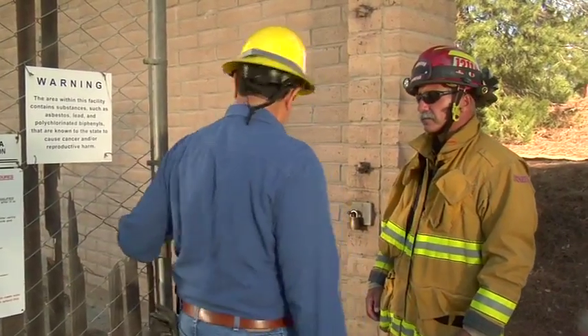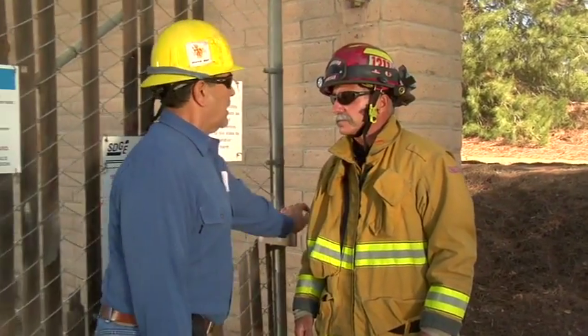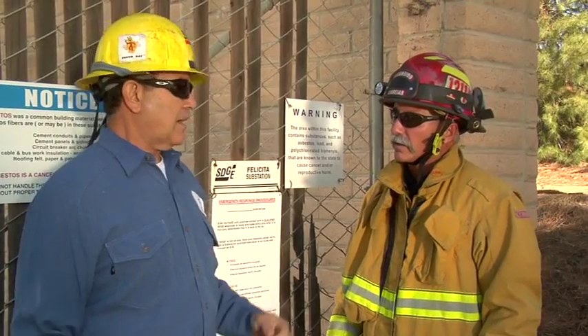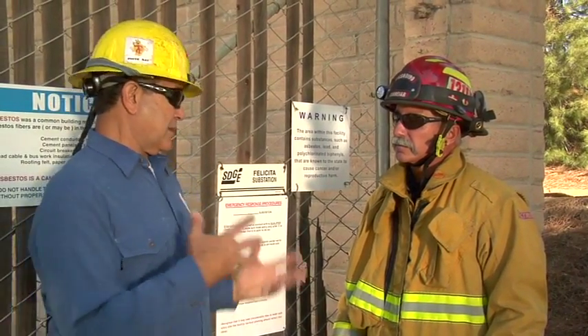I'll meet the fire personnel at the gate. It does take some time in some cases to isolate the portion where the fire is going to be fought, and I'm not going to let them in until it's safe to come in. If there is no qualified electrical worker present, firefighters need to contact their dispatch center to verify the estimated time of arrival of that qualified individual and to notify their department that this is a substation emergency.